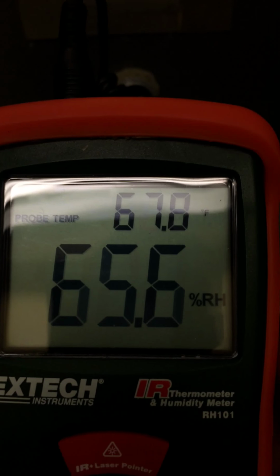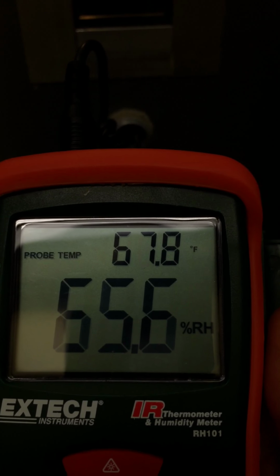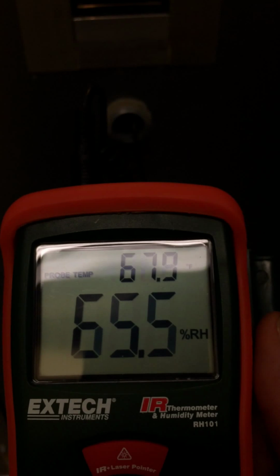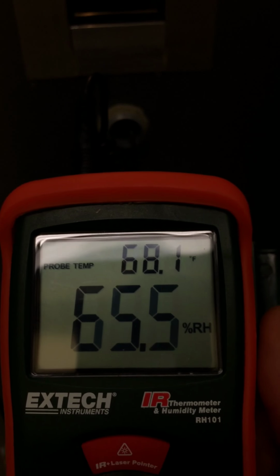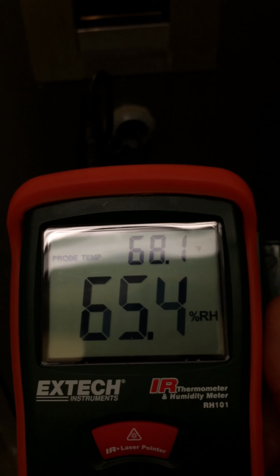Another thing that I decided on doing was to see if my discharge air temp sensor was correct by putting one of my sensors on it to see if they were reading the same. Maybe the discharge air temp sensor was incorrect. So we saw earlier we had about 69 degrees, and this meter is maybe plus or minus 3 degrees Fahrenheit. The CPO Comfort Point Open software was reading about 69, and we're at about 68 degrees Fahrenheit, 65% relative humidity right here on my probe.